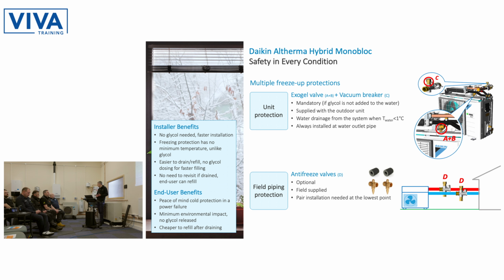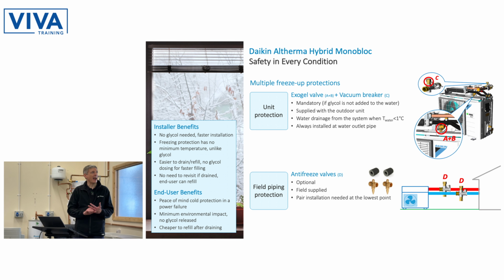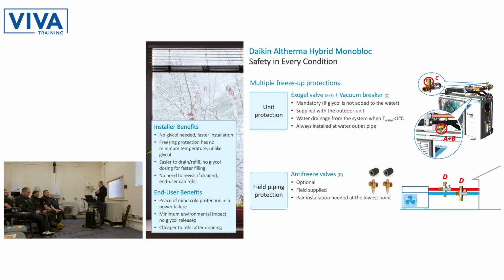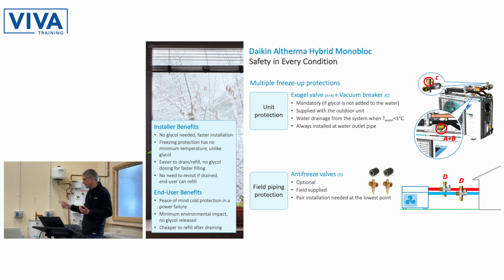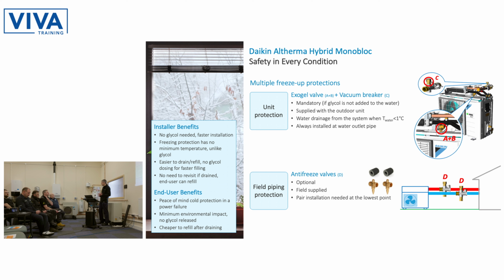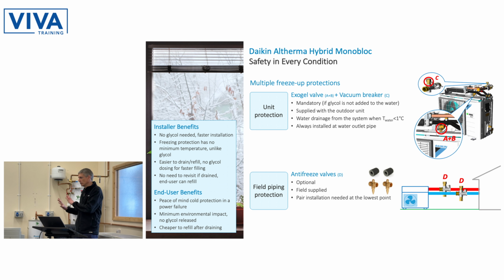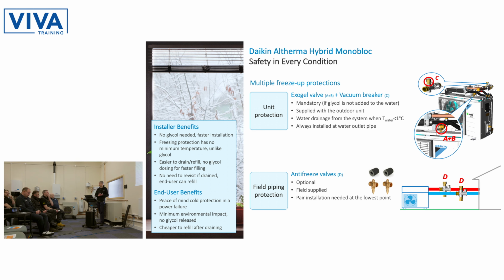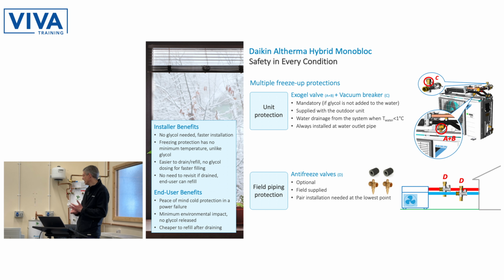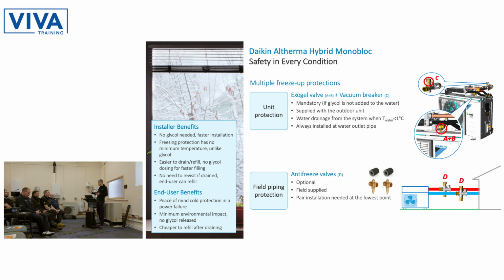Obviously, insulation is your first line of defence, but there are a number of active protections. The pump could circulate, so it literally keeps the water moving. Some heat could be put into the system, so that keeps it from freezing by putting some heat in. And obviously, it will do that automatically. It will look after that all itself. But what happens in your absolute worst case scenario? You get a power cut in the middle of winter when it's -5 outside or something. However good your insulation is, eventually it has the potential to freeze. And obviously you particularly need to make sure water doesn't freeze in the heat exchanger of the heat pump.